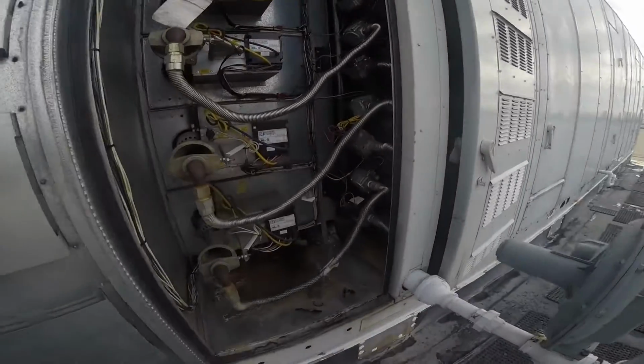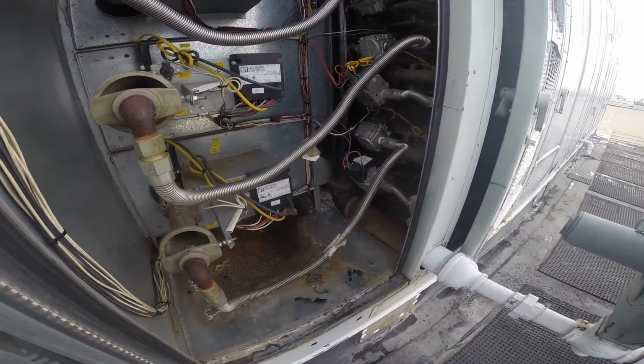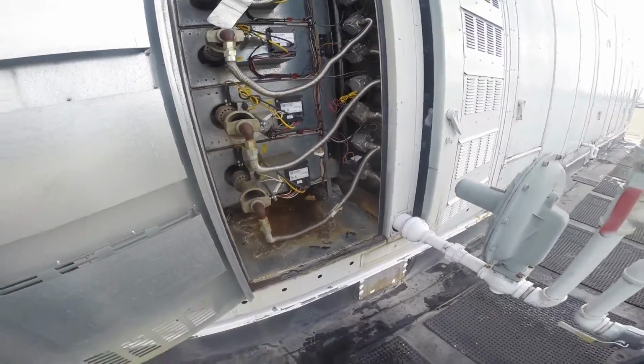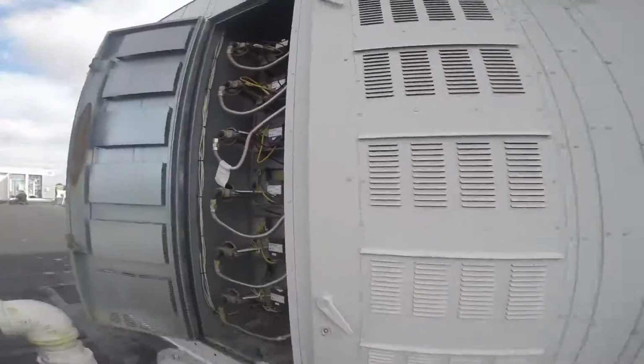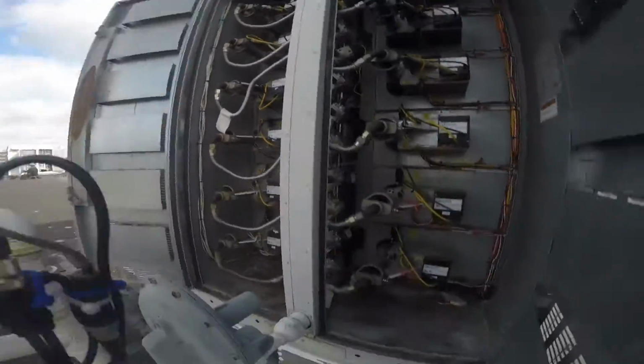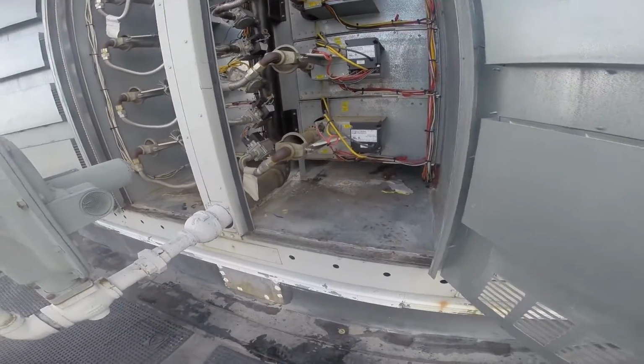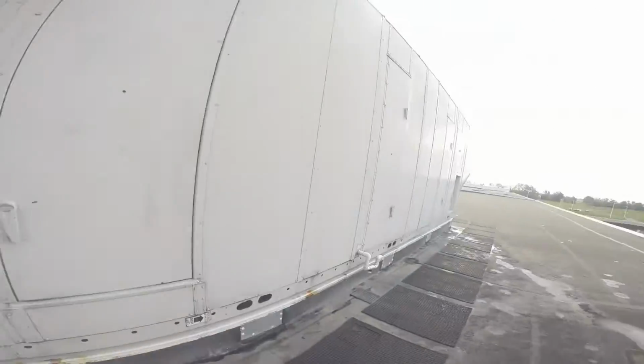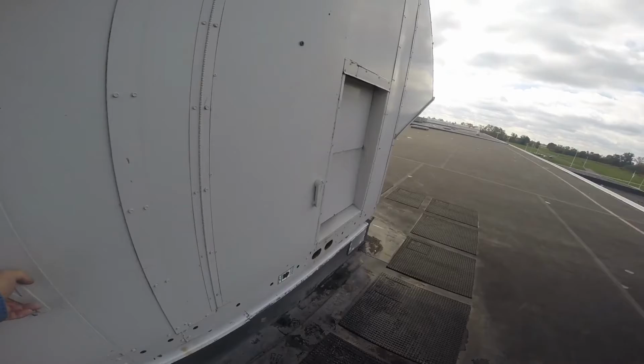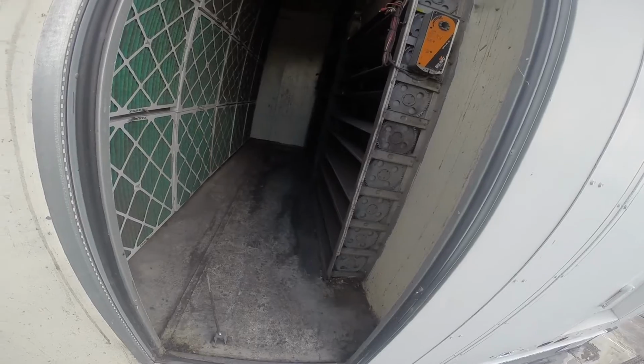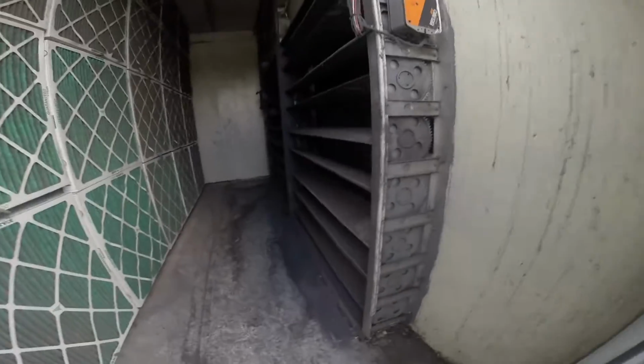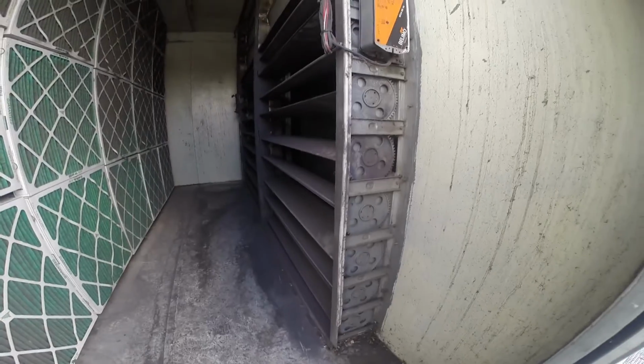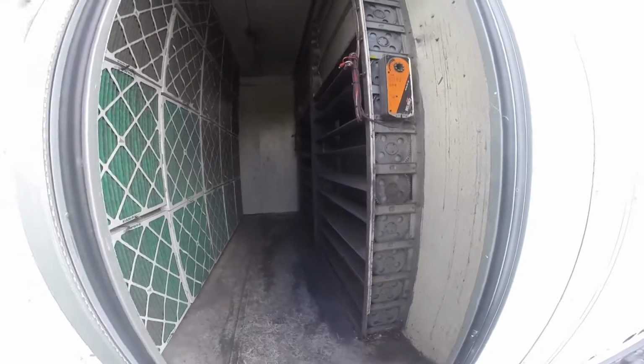Sample number 1 came from right down there in the bottom, where you see that white stuff on the bottom. Right down in there. That's where sample number 1 came from. Sample number 2 came from in here in the damper section, that black stuff, which we decided to take a sample of because maybe something's getting through the filter into that area and then chemically changing or something when it gets around the heat exchangers.